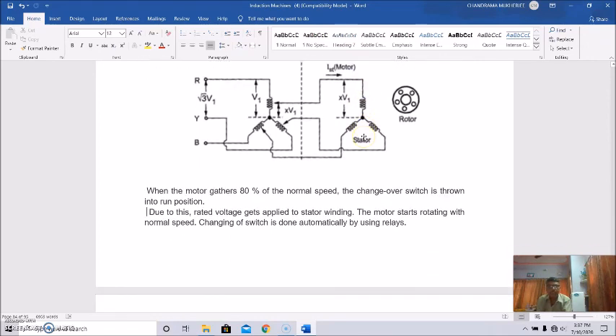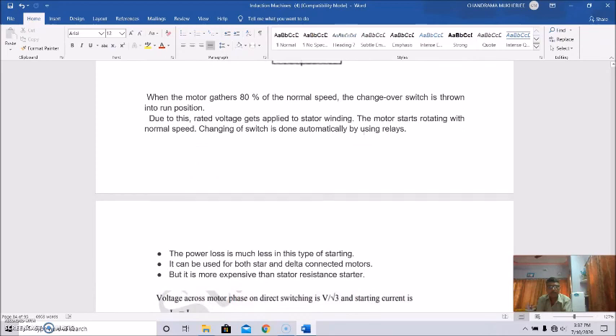It is very costly, rather than the primary resistance starter. And we can use the reduced voltage up to say 58%, or by adjusting the values of X, that's the tapping positions, we can get different reduced voltages for starting. And when the speed is around 80% of normal speed, the changeover can happen, so that the full voltage is impressed across the stator winding. This changeover is done automatically by using relays.